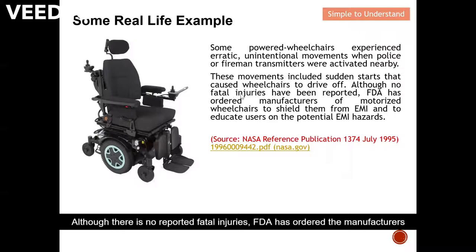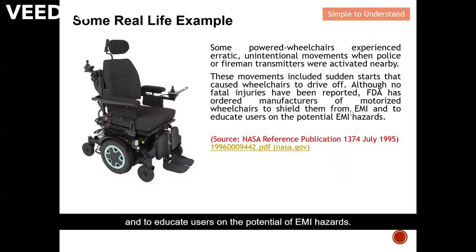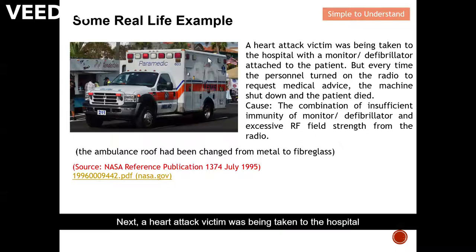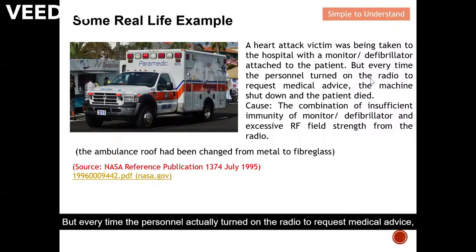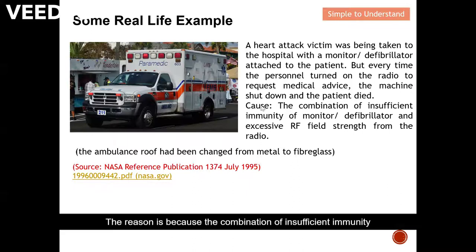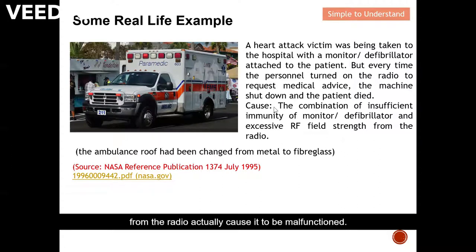Although no fatalities were reported, the FDA ordered manufacturers of motorized wheelchairs to shield them from EMI and to educate users on the potential hazards. In another case, a heart attack victim was being taken to hospital with a monitor attached, but every time personnel turned on the radio to request medical advice, the machine shut down and the patient died. The cause was insufficient immunity from the monitoring equipment combined with excessive RF signal strength from the radio, leading to malfunction. The short-term solution was changing the ambulance roof from metal to fiberglass.